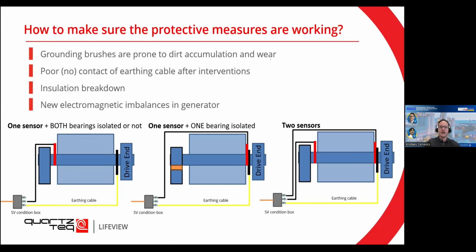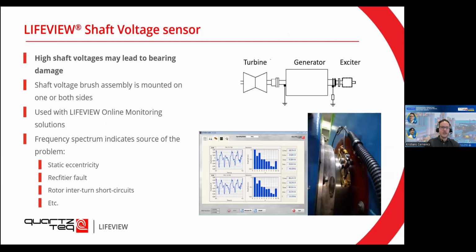or maybe you need to clean the shaft because there's too much dirt accumulation that the grounding brush cannot work anymore. And what we provide is, again, multiple different solutions depending on the machine. If there is already insulation, where the access points are, we can install one sensor on the drive end, we can install one sensor on the other end, or we can install two sensors on both ends if it's available. And then depending on this, you can make the analysis of the health of your shaft. So in general, high shaft voltages might lead to bearing damage. To monitor the health of your machine and monitor if your countermeasures are working, we would need to install additional sensors. These sensors can be used with online monitoring solutions that Quartzteq is providing.